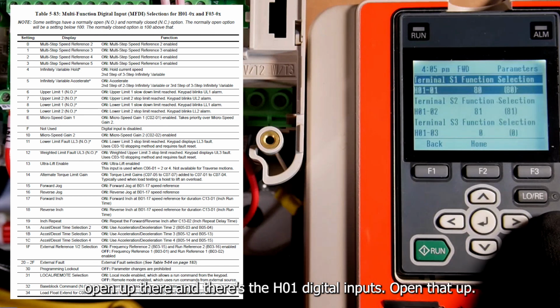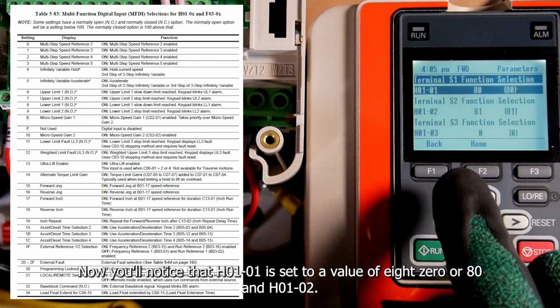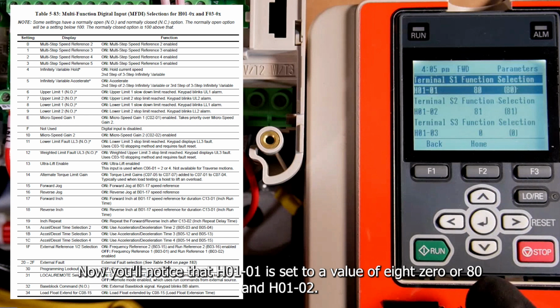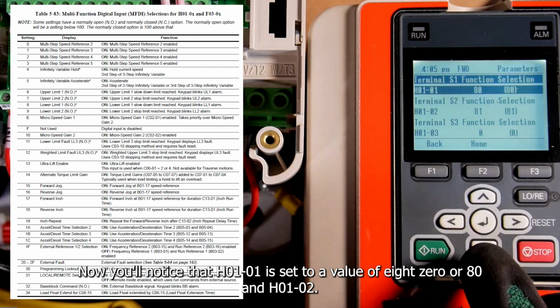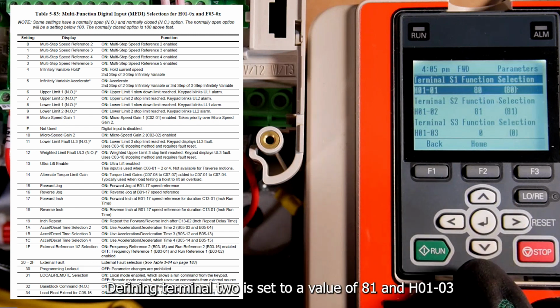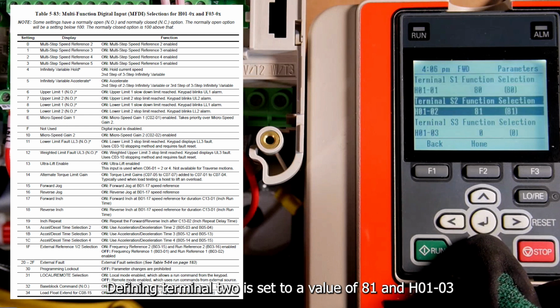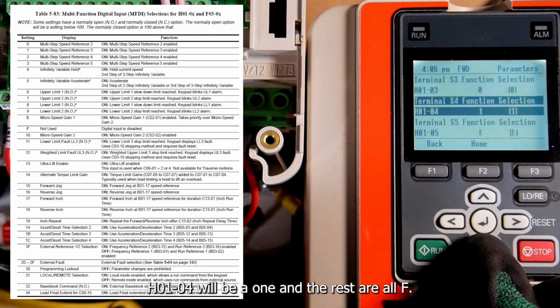Open that up. Now you'll notice that H01-01 is set to a value of 80. And H01-02, defining terminal 2, is set to a value of 81. And H01-03 is a 0. And H01-04 will be a 1. And the rest are all Fs.